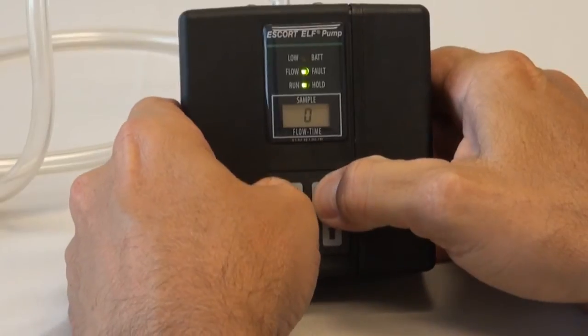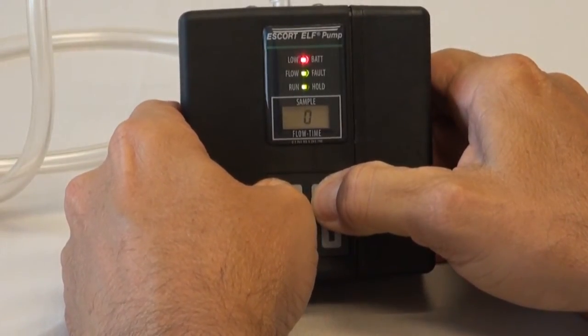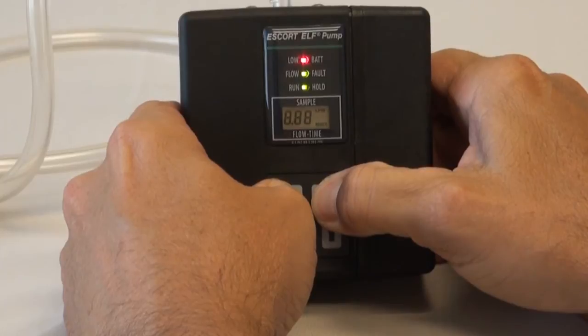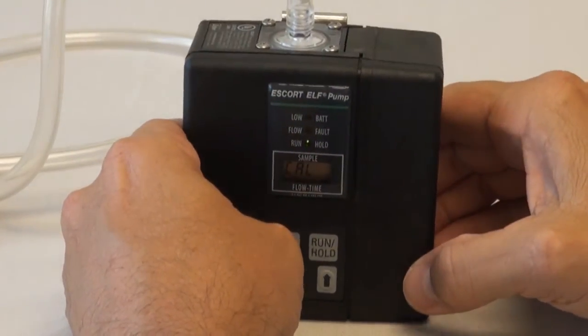As the pump goes through its self-check sequence and the LED lights illuminate, press and hold the on-off and the run-hold button simultaneously until the display reads CAL. Immediately release both buttons.